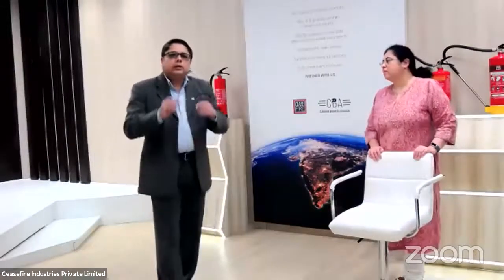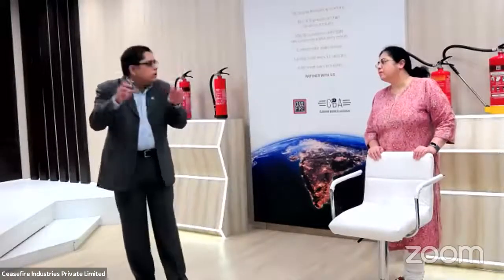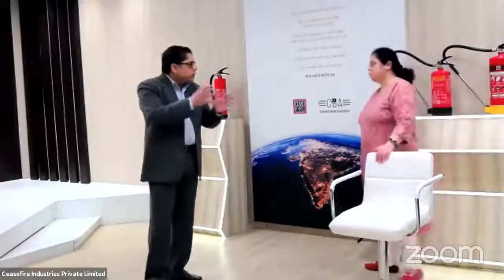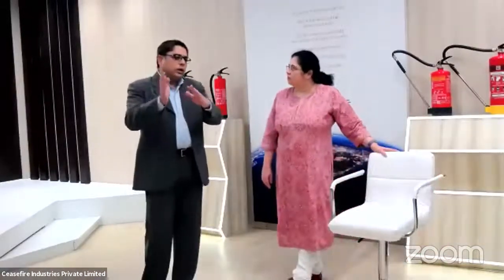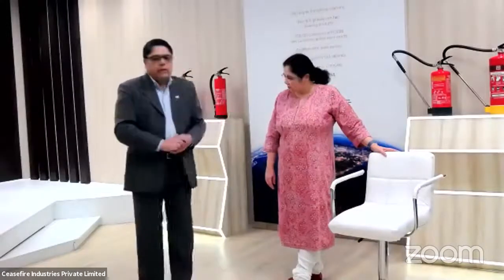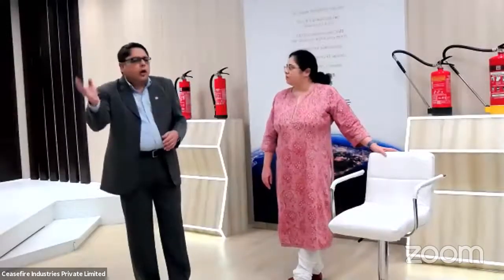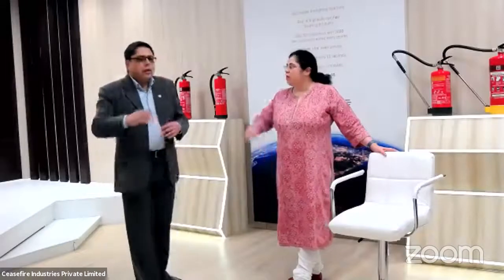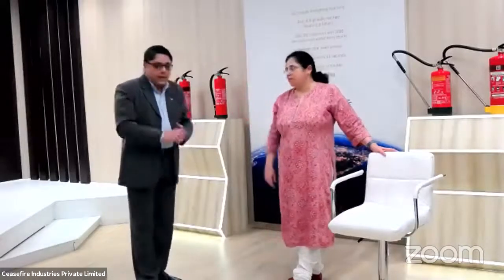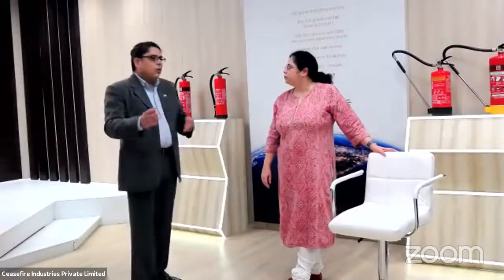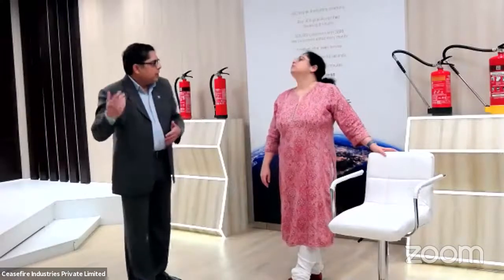Here what happens is there's a tube which is connected to your extinguishing cylinder, and this tube is pressurized and it is equivalent to the pressure within the cylinder. And this runs unobtrusively throughout the panel. And why unobtrusively? Because we don't want to trouble people with the daily maintenance requirements.